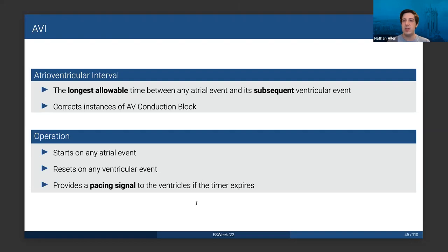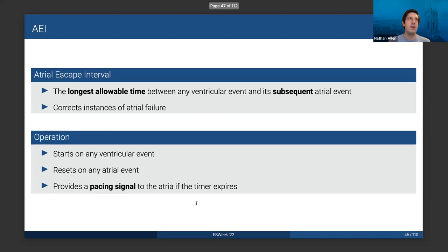PVARP — the postventricular atrial refractory period — is very similar: it starts on a ventricular event, and during that time all atrial signals are ignored and recorded as atrial refractory sense signals. The common reason is crosstalk: the ventricles are large and when they contract, their depolarization is easily picked up by the sensitive atrial lead. AVI starts on an atrial event; if we get a ventricular event, we reset the timer. If the timer expires and URI has also finished, then we issue a ventricular pacing signal — that's the AVI extension. AEI is similar but opposite: starts on a ventricular event, resets on an atrial event, and corrects behaviors like sinoatrial node failure.